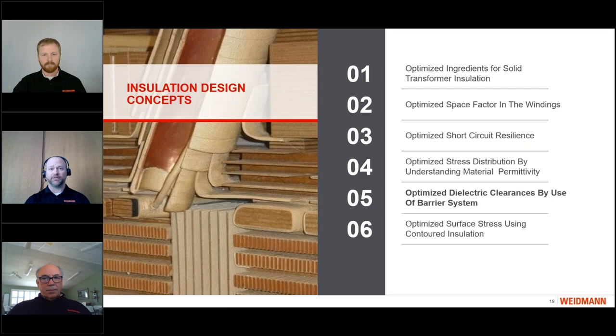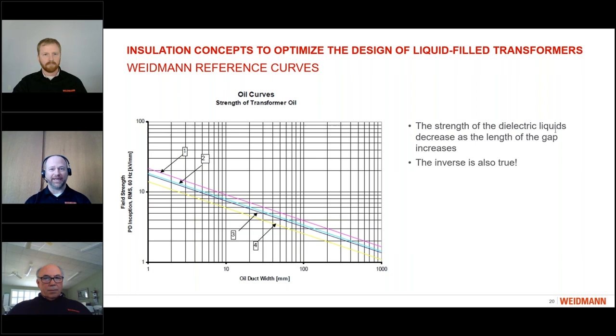Oh, nope, I lied to you. That's the slide after. The first way to do this, and Brad showed us this a little bit on the previous slides where he was showing field plots for dielectric analysis, there's a way to interpret the oil gaps by use of what's called a Weidmann reference curve. These have been used in the industry for many, many years now and have been backed up by lots of practical use and studies across the entire world.